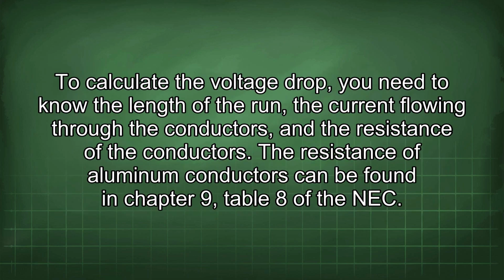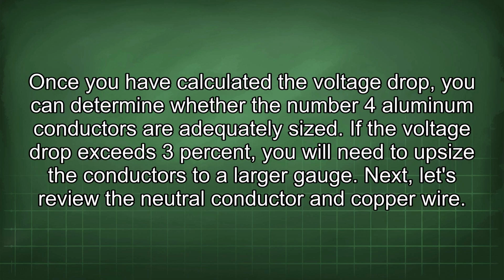To calculate the voltage drop, you need to know the length of the run, the current flowing through the conductors, and the resistance of the conductors. The resistance of aluminum conductors can be found in Chapter 9, Table 8 of the NEC. Once you have calculated the voltage drop, you can determine whether the number 4 aluminum conductors are adequately sized. If the voltage drop exceeds 3%, you will need to upsize the conductors to a larger gauge. Next, let's review the neutral conductor and copper wire.